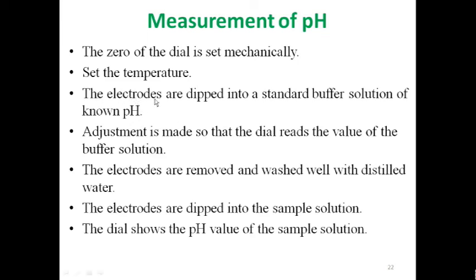The electrodes are dipped into the standard solution. First, we take the standard buffer solution of pH 7 and adjust it to pH 7.